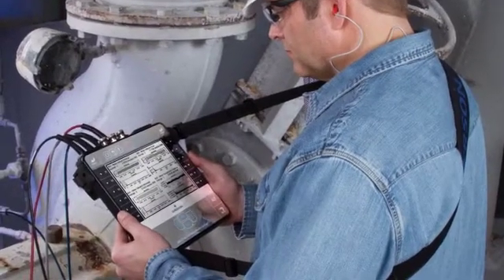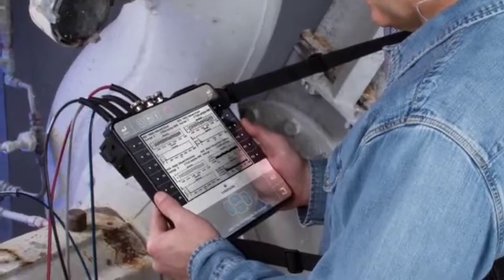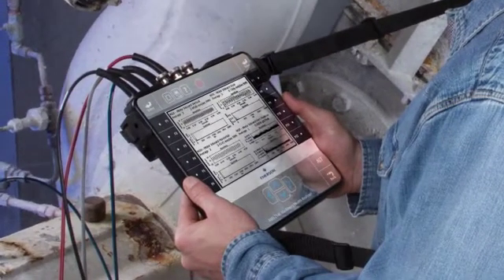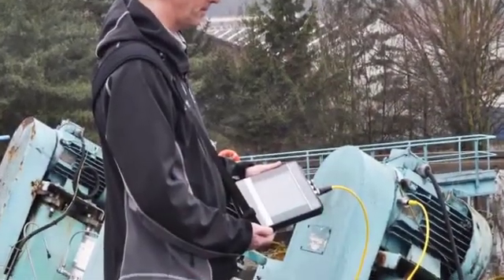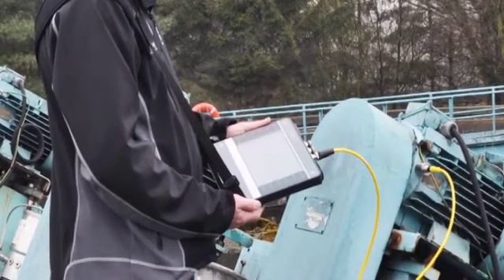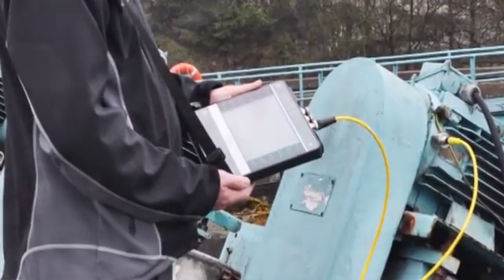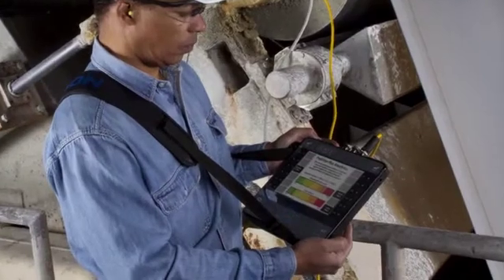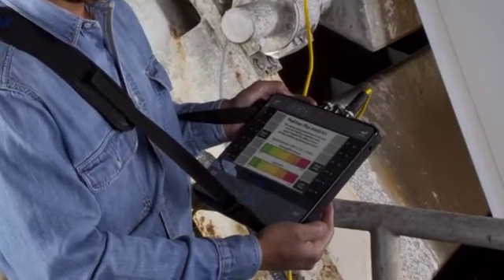AMS 2140, Coast Down Peak and Phase Measurements. In this tutorial, I will show you how to measure coast down peak and phase using the AMS 2140. These measurements are normally used to detect resonance frequencies on rotating equipment.